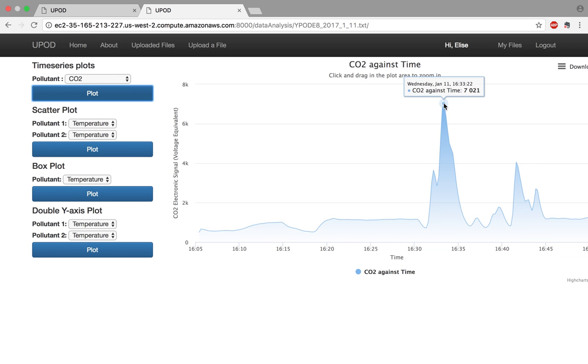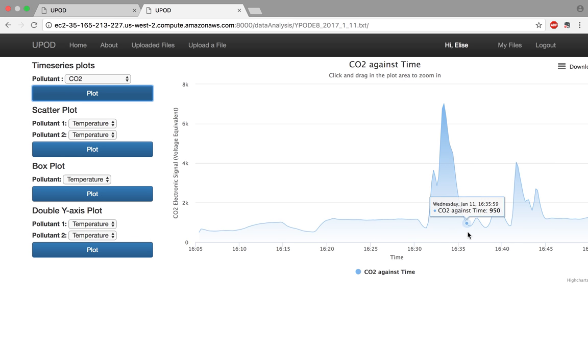We can't say how much concentration the pod was exposed to at that time. What we can say from plotting the raw signal in voltage units is that at this peak, we have a higher concentration exposed to the pod than later on in time where we only have 835 voltage units.